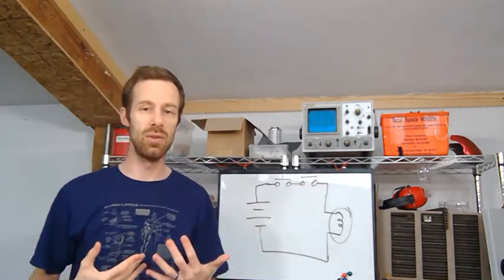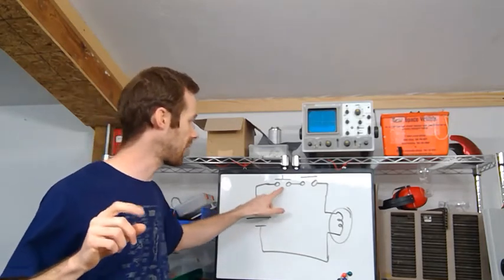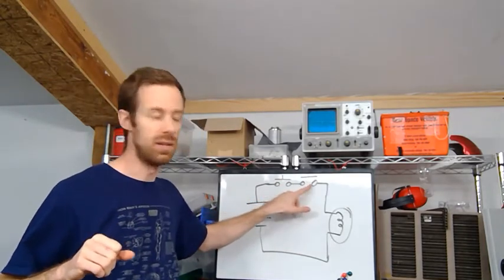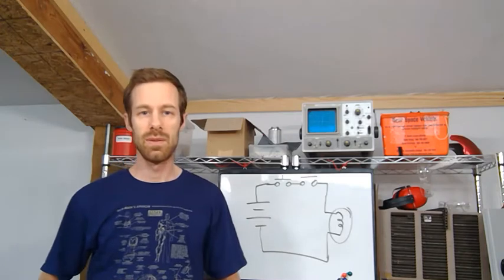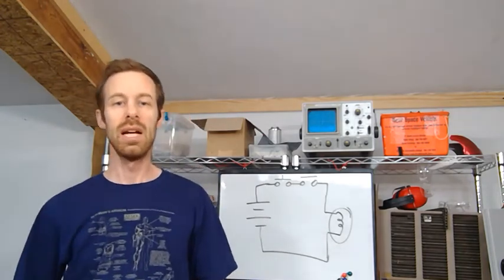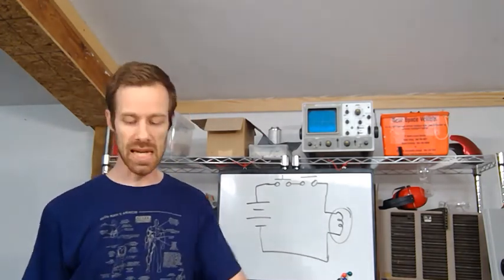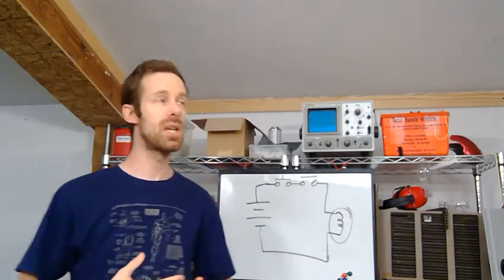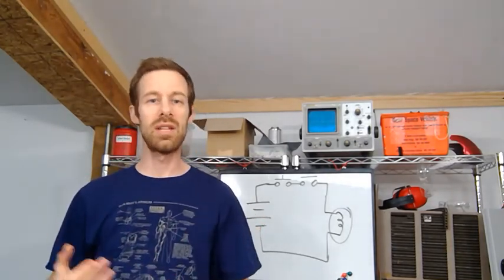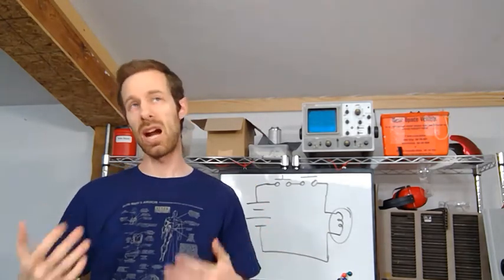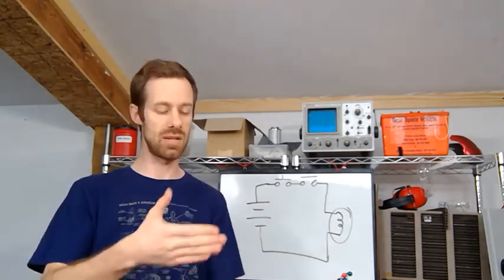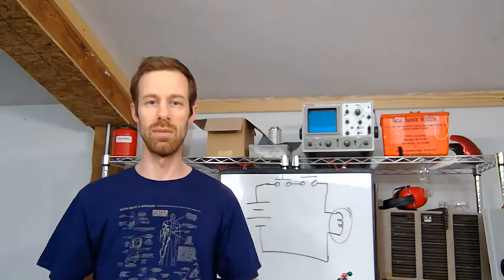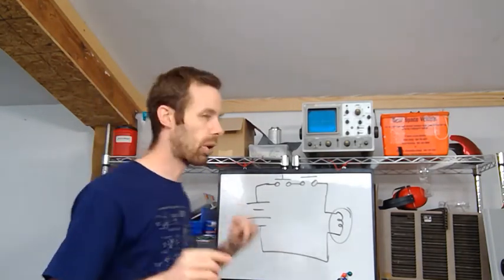Or as we would say that in logic, we would say press this button and this button to get the load to activate. We call that an AND circuit. In logic descriptions, we use AND and OR quite frequently when we're trying to describe what happens because our brains work logically. So they design logical circuits to be able to have kind of the same notation. It means that if I press this one and this one, it will turn on. Now, these are called normally open.